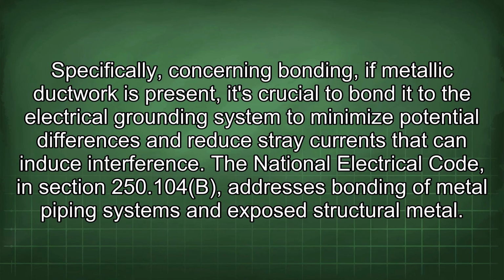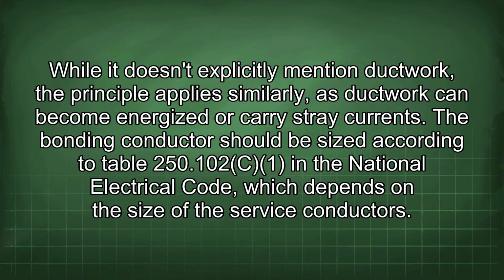Specifically concerning bonding, if metallic ductwork is present, it's crucial to bond it to the electrical grounding system to minimize potential differences and reduce stray currents that can induce interference. The National Electrical Code, in section 250.104(B), addresses bonding of metal piping systems and exposed structural metal. While it doesn't explicitly mention ductwork, the principle applies similarly, as ductwork can become energized or carry stray currents.